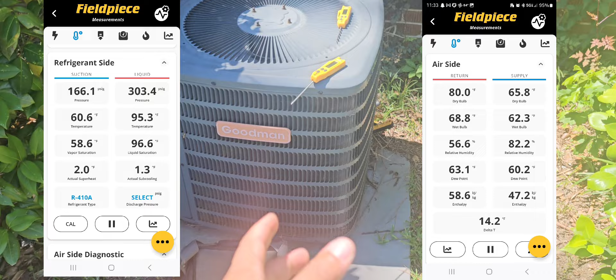Zillow is posting this house right now at around 2,000 square feet. I'm about to walk around and see exactly what's up with it, because if that's true, I'm fairly certain this 3-ton is undersized. Even if it's not 2,100 square feet like it says on Zillow, I'm pretty sure this should have been closer to a 3.5 to 4-ton. I think Zillow might have overshot this by maybe 300 square feet.